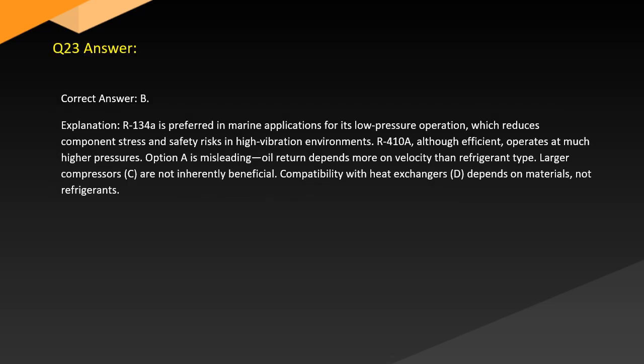Answer. Correct answer: B. Explanation: R134a is preferred in marine applications for its low pressure operation, which reduces component stress and safety risks in high vibration environments. R410A, although efficient, operates at much higher pressures. Option A is misleading. Oil return depends more on velocity than refrigerant type. Larger compressors (C) are not inherently beneficial. Compatibility with heat exchangers (D) depends on materials, not refrigerants.